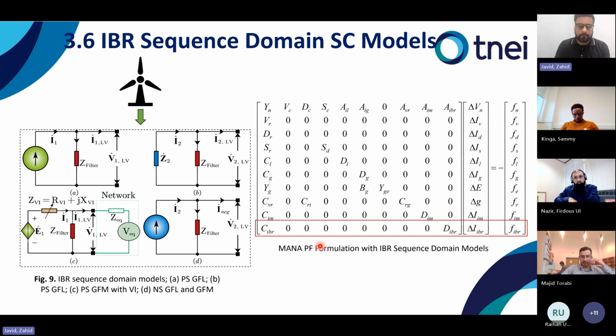For example, if we want to adapt the negative sequence to follow the German grid code, we know that I2 should be k times V2, where k is equal to I2 over V2, which is nothing but 1 over Z. So if we set the value of the negative sequence impedance to 1 over k, it can follow the German grid code easily.